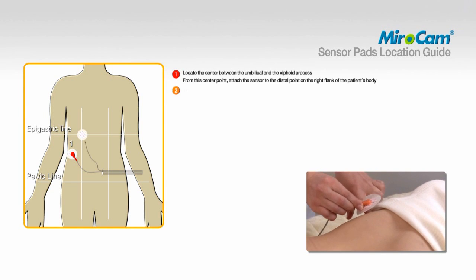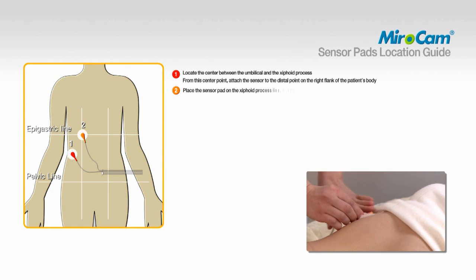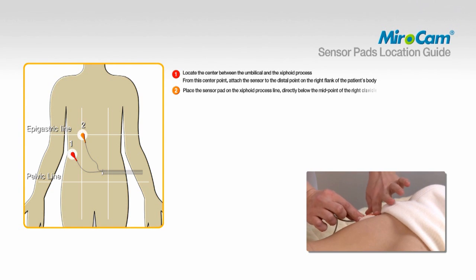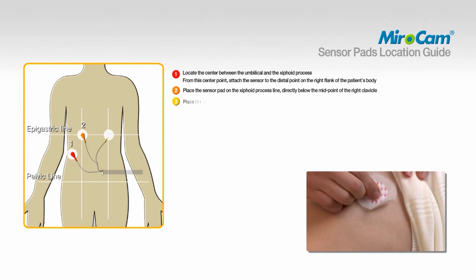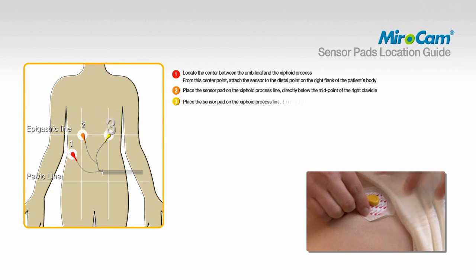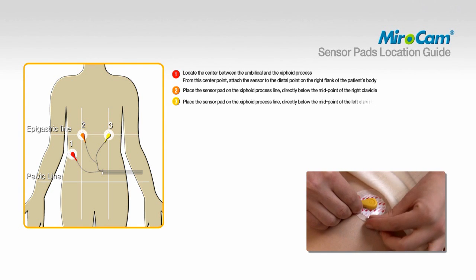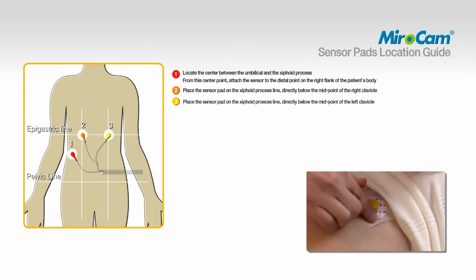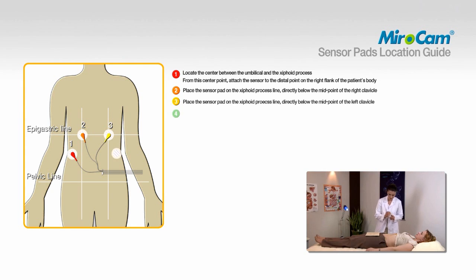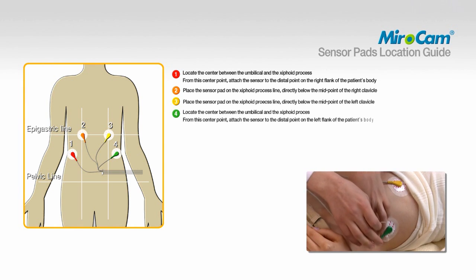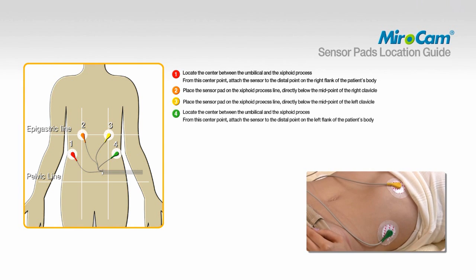To attach pad number 2, place the sensor pad on the xiphoid process line, directly below the midpoint of the right clavicle. To attach pad number 3, place the sensor pad on the xiphoid process line directly below the midpoint of the left clavicle. To attach pad number 4, locate the center between the umbilical and the xiphoid process. From this center point, attach the sensor to the distal point on the left flank of the patient's body.